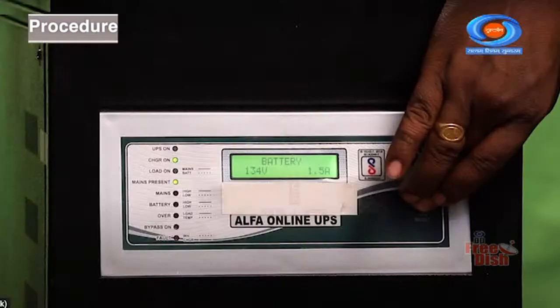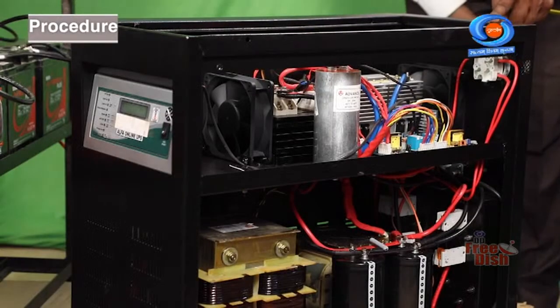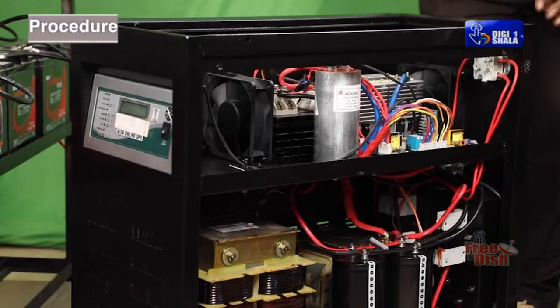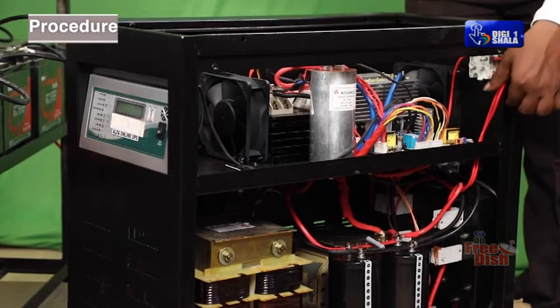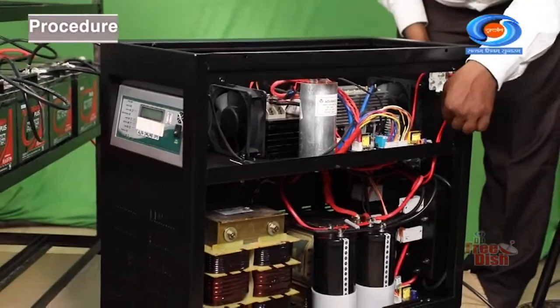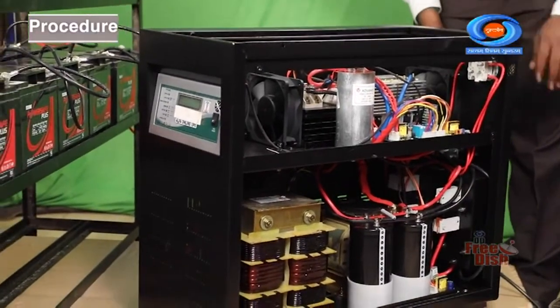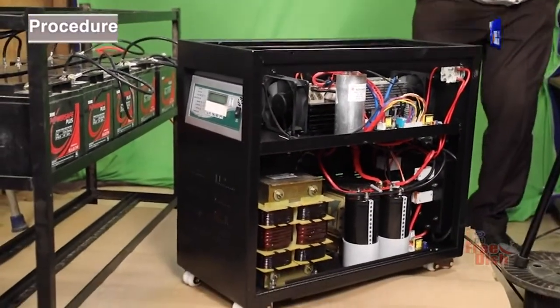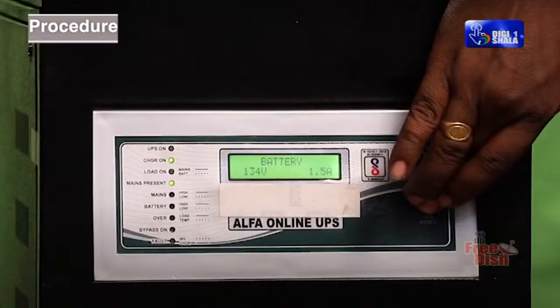To switch off the UPS, press and hold the on-off test silence button for more than 3 seconds until the line normal or backup LED is off. Check the condition of the switch or backup LED, yellow LED, or press the switch for more than 3 seconds, and rectify the problem if the UPS does not switch off. Press the on-off test silence switch for more than 3 seconds to switch off the UPS and battery.